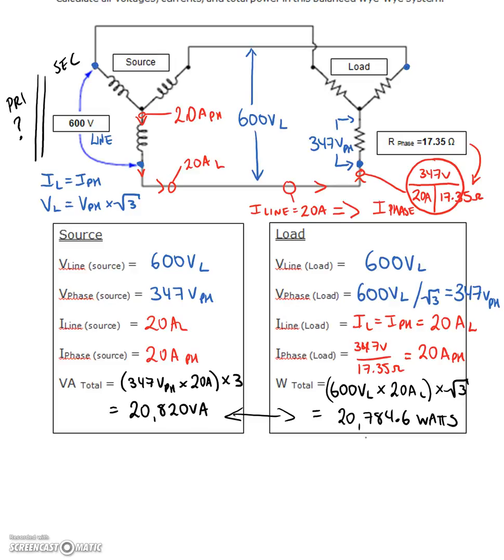So again, we took the source voltage of 600 volts. That was our line voltage. That came across. 347 volts on the phase divided by 17.35 gives us 20 amps on the phase. Phase and line current are identical. So 20 amps comes all the way through. Then we found our total wattage by taking line voltage times line current times root three or phase voltage times phase current times three. And we found that these guys were identical.